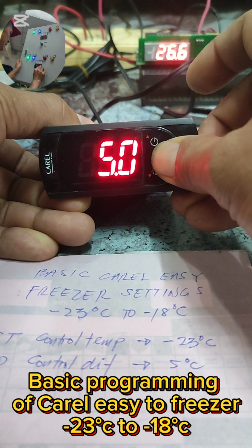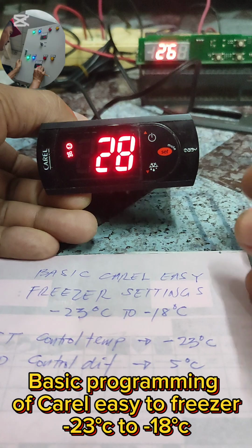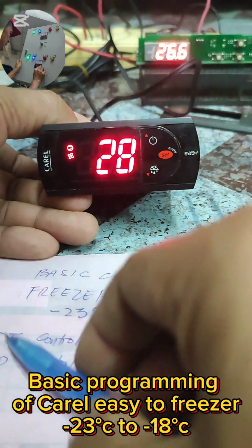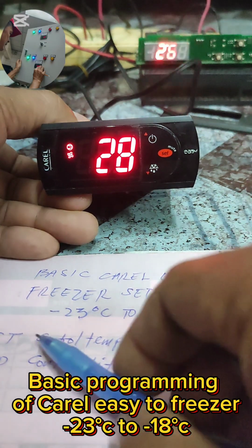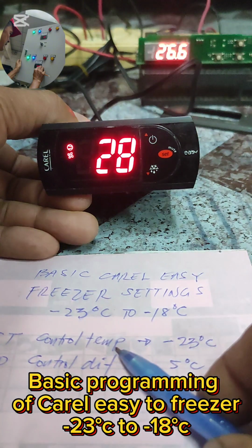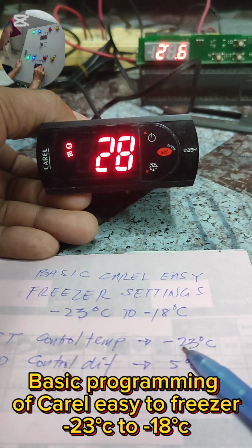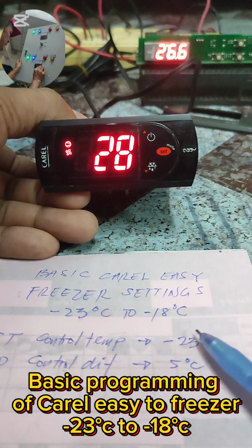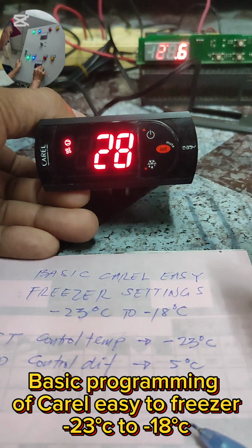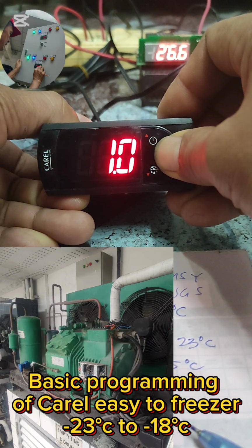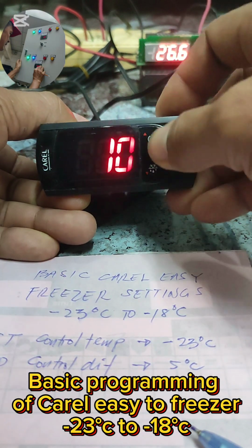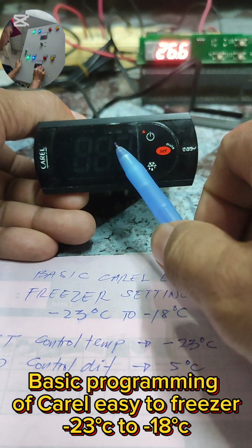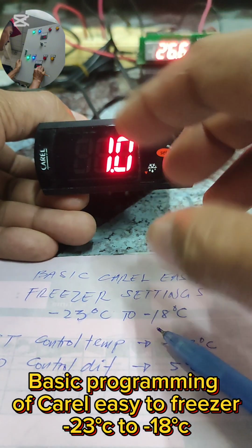Just long press it to go back to display, and we're going to change the set point, which is the control temperature, and that is negative 23. Upon reaching negative 23, the compressor will cut off once the display temperature starts blinking.